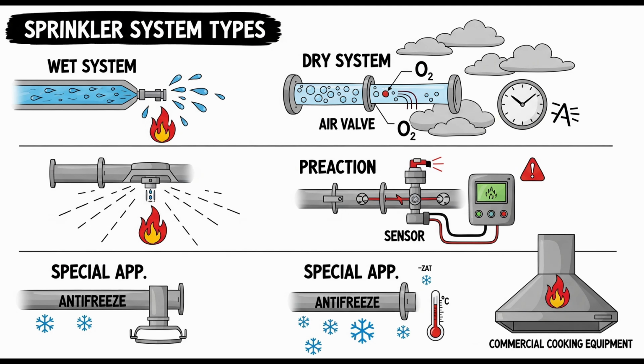When the detection system goes off, the valve opens, and water pours out of all the open heads at once. Okay, the source covers general requirements applicable to both pre-action and deluge. What are some of those? First, all components of the release system, whether they use pneumatic, air, hydraulic, water, or electrical signals, must be compatible with each other. Everything has to work together smoothly.